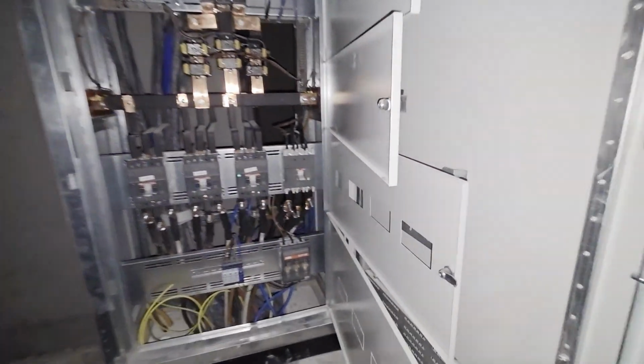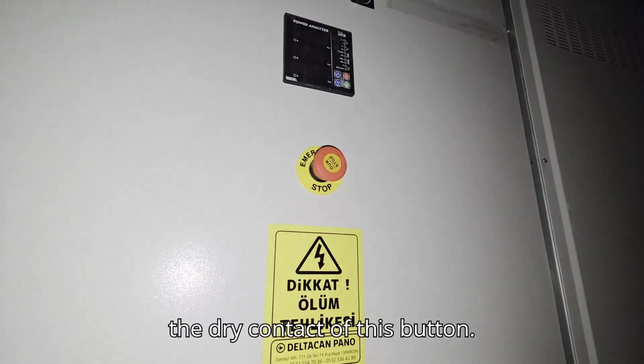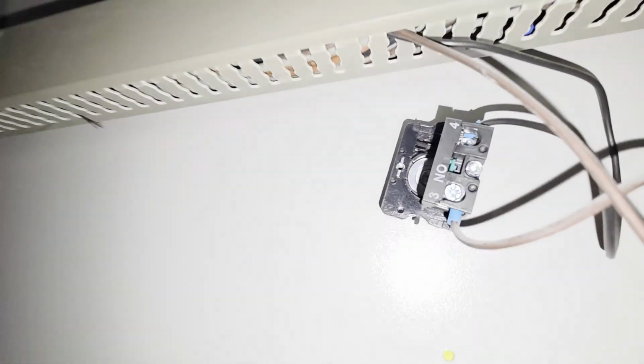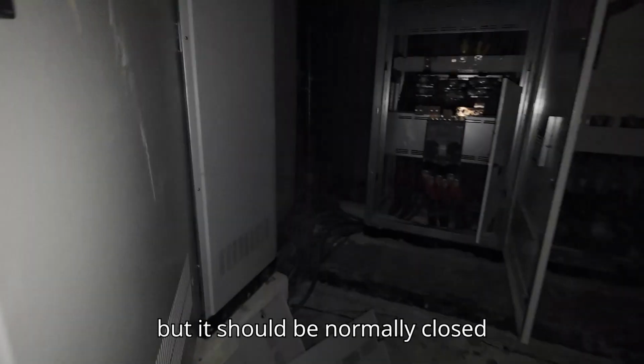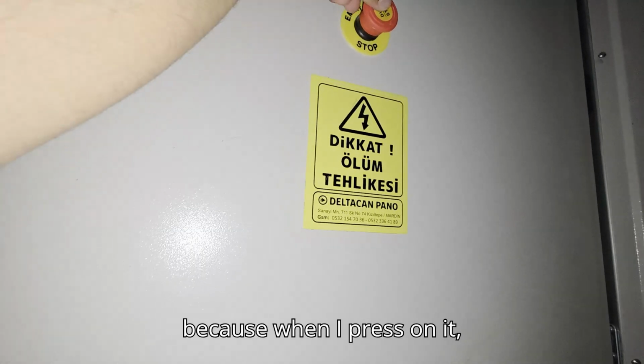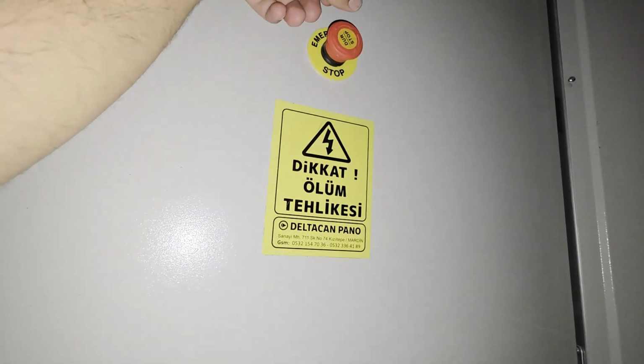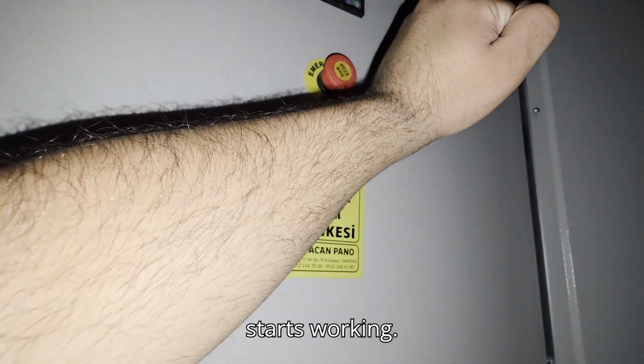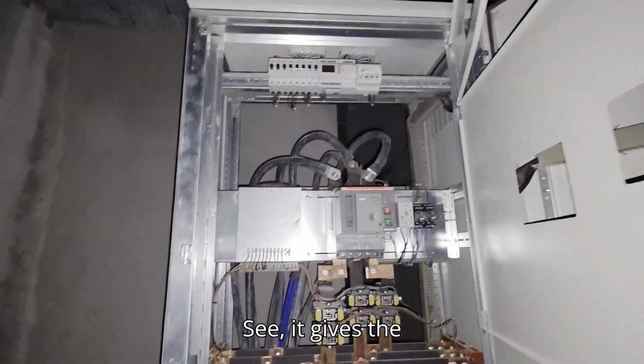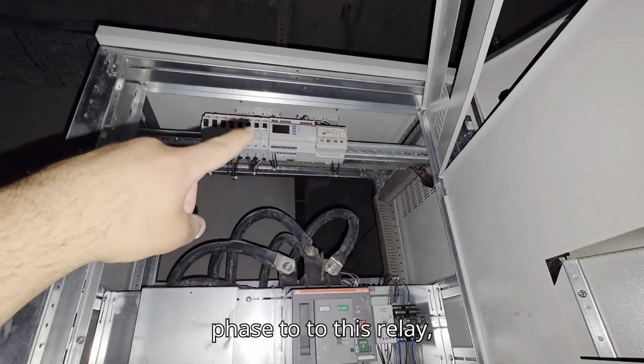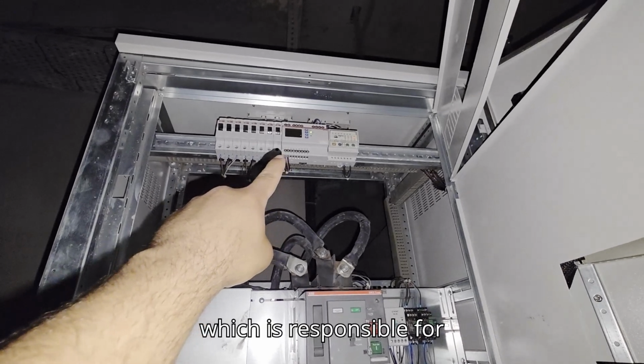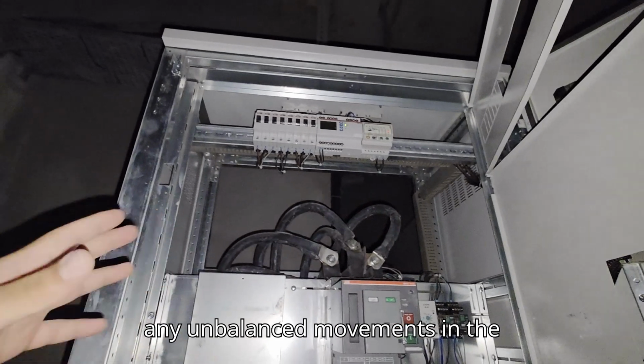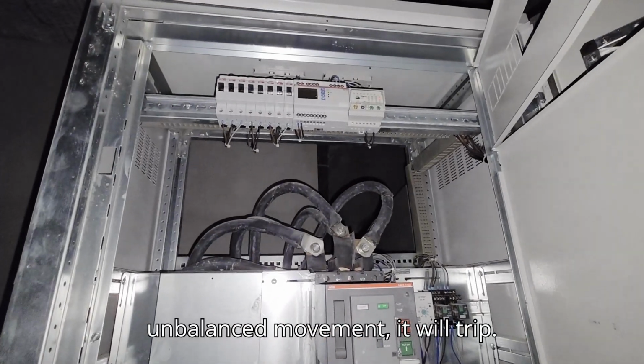For example, this is the emergency stop button. The dry contact of this button is not correct. Basically, they have used normally open, but it should be normally closed, because when I press on it, the panel works and the motor, the circuit breaker, starts working. See, it gives the phase to this relay, which is responsible for any unbalance movements in the grid. If there is any unbalanced movement, it will trip.